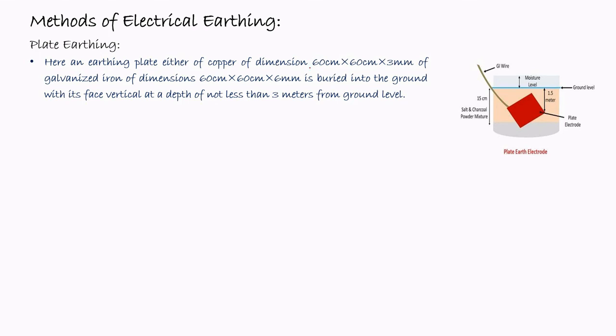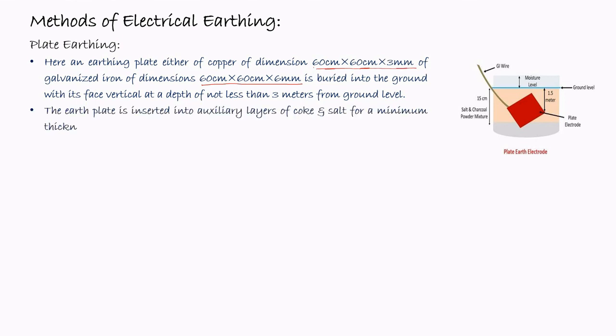The dimension of the plate is standard. If it is made of copper, then this will be the dimension of the plate, and if it is made of galvanized iron, then this will be the dimension of the plate. This is the length, width and thickness, and this is also the length, width and thickness. The earth plate is inserted into auxiliary layers of coke and salt for a minimum thickness of 15 centimeter. So again the salt and coke powder or the charcoal powder is placed here and it is around 15 centimeter.